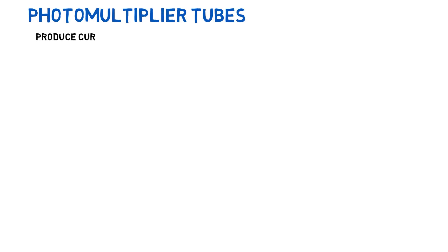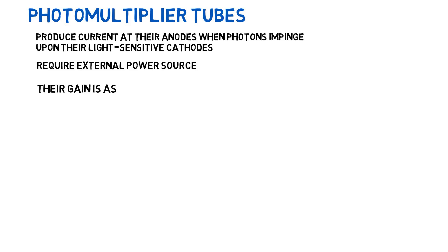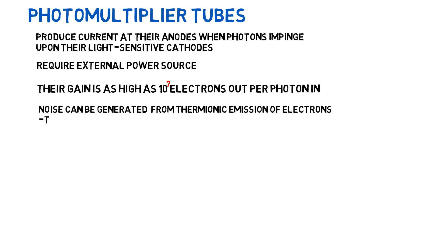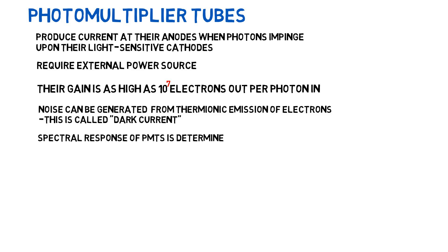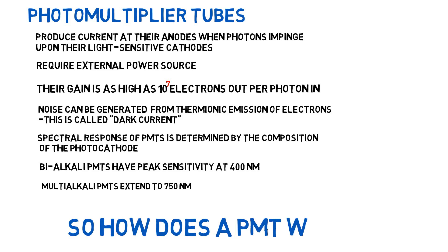Let's discuss photomultiplier tubes. PMTs produce current at their anodes when photons impinge upon their light-sensitive cathodes. They require an external power source. Their gain is as high as 10 to the 7 photoelectrons out per photon in. Noise can be generated from thermionic emission of electrons — what we call dark current. The spectral response of PMTs is determined by the composition of the photocathode. If it's bialkali, the PMT has a peak sensitivity around 400 nanometers; if it's multialkali, it extends to about 750 nanometers.